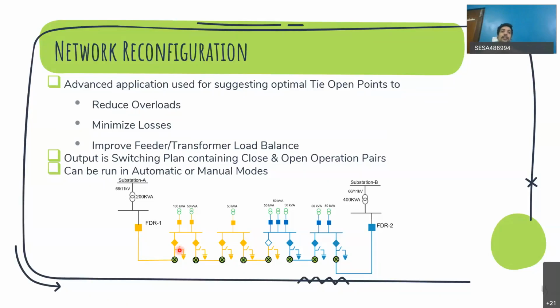That is load shedding. Then the next option is network reconfiguration. This is also an advanced application used for suggesting optimal tie open points to reduce overloads in the network, minimize the losses, and improve the feeder or transformer load balance. Okay. The output in the case of this application is again a switching plan containing close and open operations. Again, this can also be run in automatic or manual.